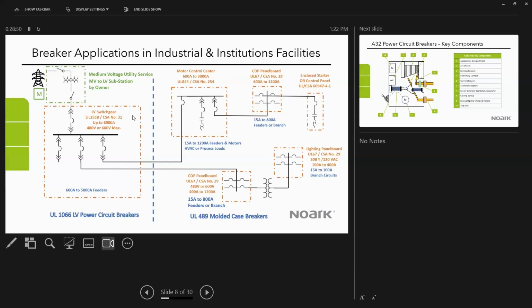There's another layer of assembled equipment here, and it's a low voltage switchgear. It's under UL 1558, and it almost exclusively uses power circuit breakers approved to UL 1066. Those breakers are in the ampacity range of 600 to 5,000 amps. And these assemblies can become very complex because in larger facilities, say a data center, for example, not only will you have the utility service feed coming in, but you could also have a UPS and one or more backup generators that are attached to this power distribution system. So that coordination of all those sources and all of the loads is done within this low voltage switchgear assembly.